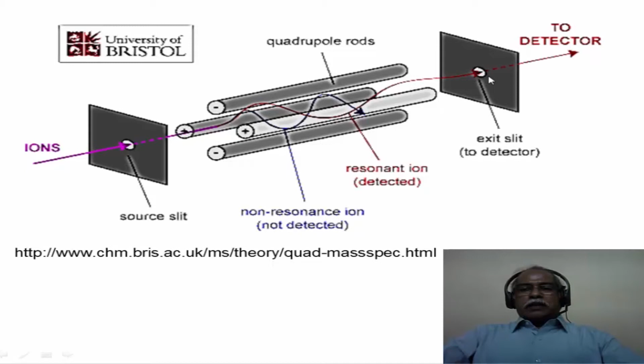Only a certain M/Z ratio mass will pass through this analyzer for a given applied voltage and radio frequency voltage. All the other M/Z values will get destroyed by hitting the walls. So by scanning the voltage, one can take one mass at a time and pass it through the slit here into the detector, and thereby detect the mass of this ion. This is given in another diagrammatic representation here.